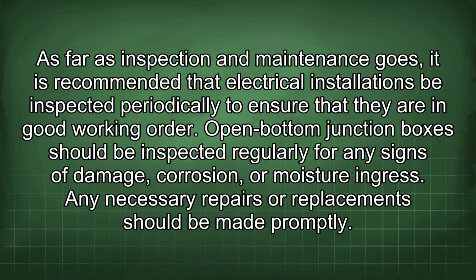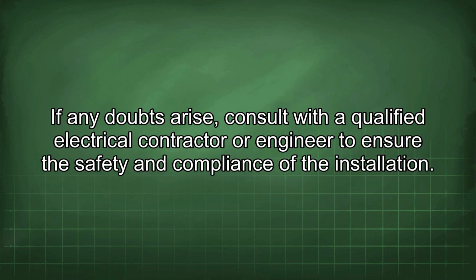As far as inspection and maintenance goes, it is recommended that electrical installations be inspected periodically to ensure that they are in good working order. Open-bottom junction boxes should be inspected regularly for any signs of damage, corrosion, or moisture ingress. Any necessary repairs or replacement should be made promptly. If any doubts arise, consult with a qualified electrical contractor or engineer to ensure the safety and compliance of the installation.